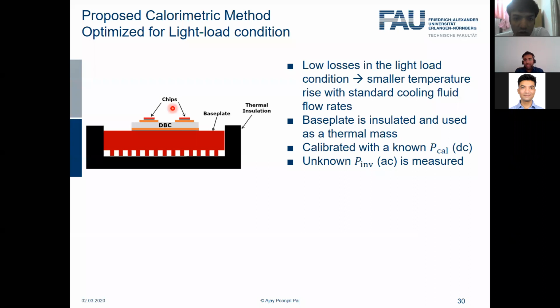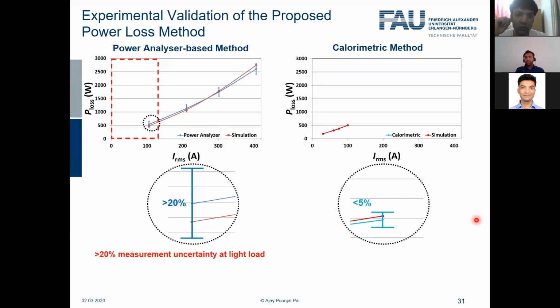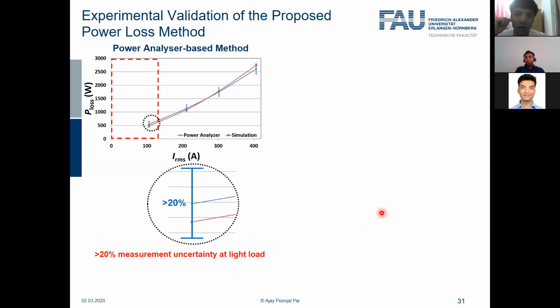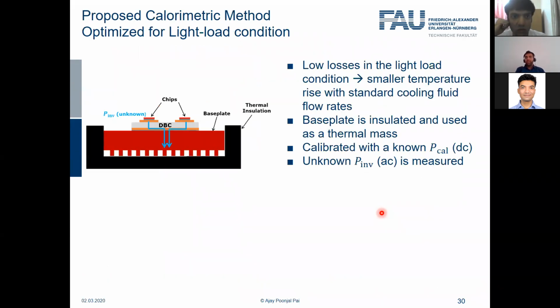That would lie somewhere here on the substrate, and it would measure close to the chip temperature. But you could also, for example, insert a thermocouple either into the base plate or better close to the chips, and perform this method. It does not really depend too much on the sensor itself. Of course the accuracy of the sensor should be good - otherwise this 5% might be higher, so you might have 10% instead of 5%. But because the method can principally be used for any kind of temperature sensor. Understood.